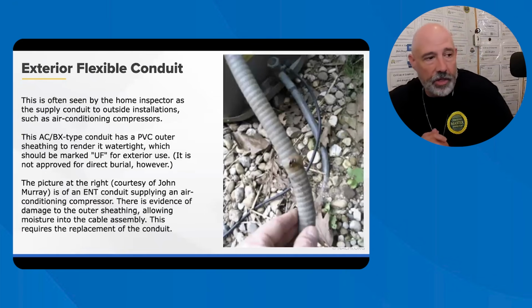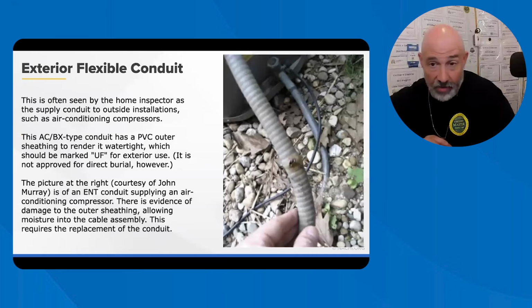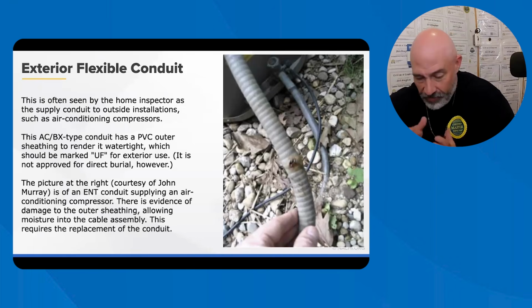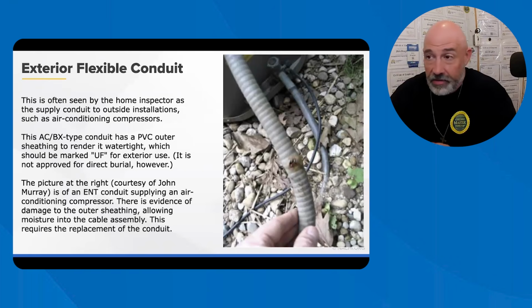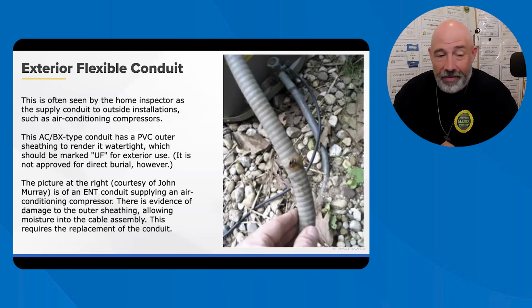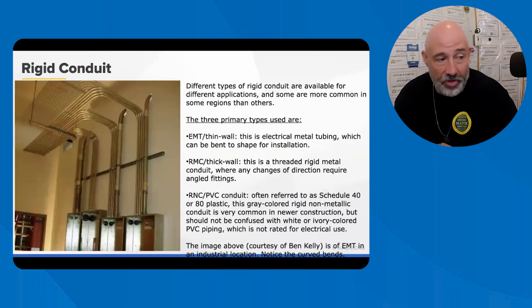Here are a couple of things that you should look for, especially with the flexible conduit. A lot of times those are water resistant. Normally you'll see them at air conditioners. Damage to the outer sheathing should be called out. I see this every once in a while. It doesn't happen too often, but I do see it. And make sure that you're being very vigilant on what you're looking at and telling your customers exactly what you see. You don't want to allow moisture in there. You don't want anybody to get shocked or electrocuted. You just don't want to have it.